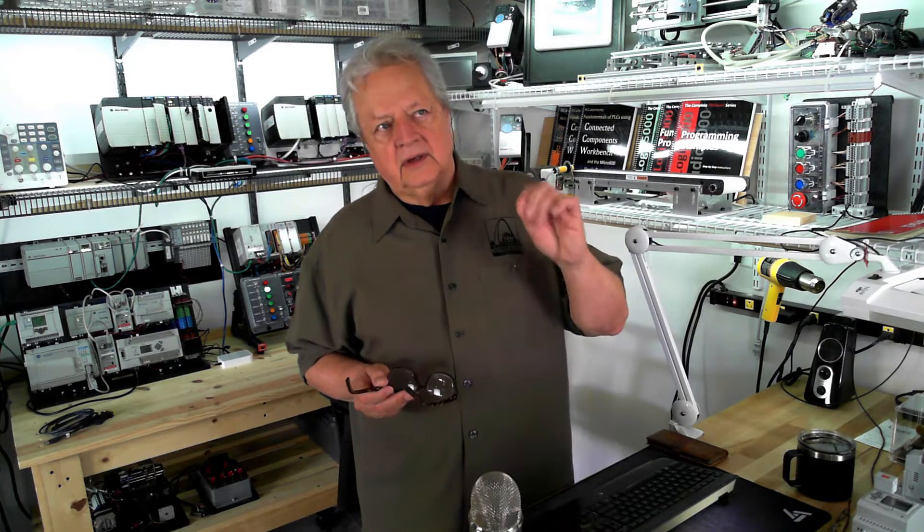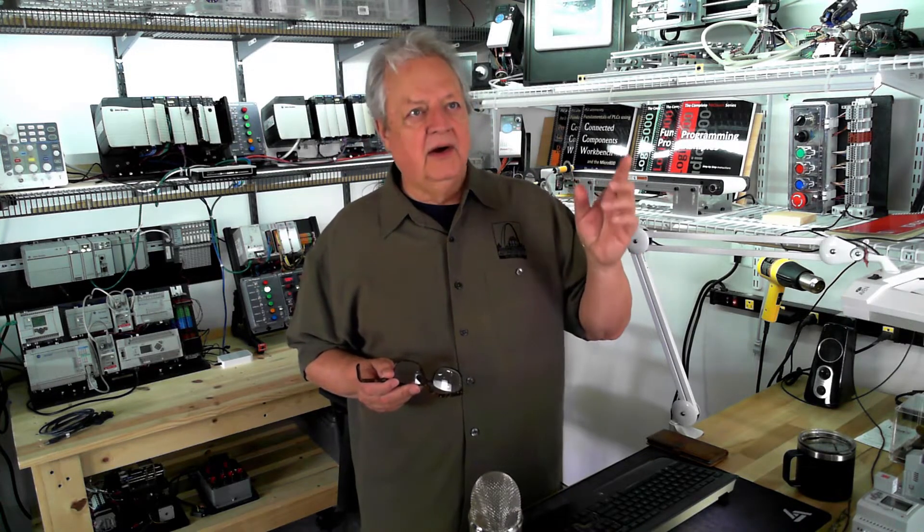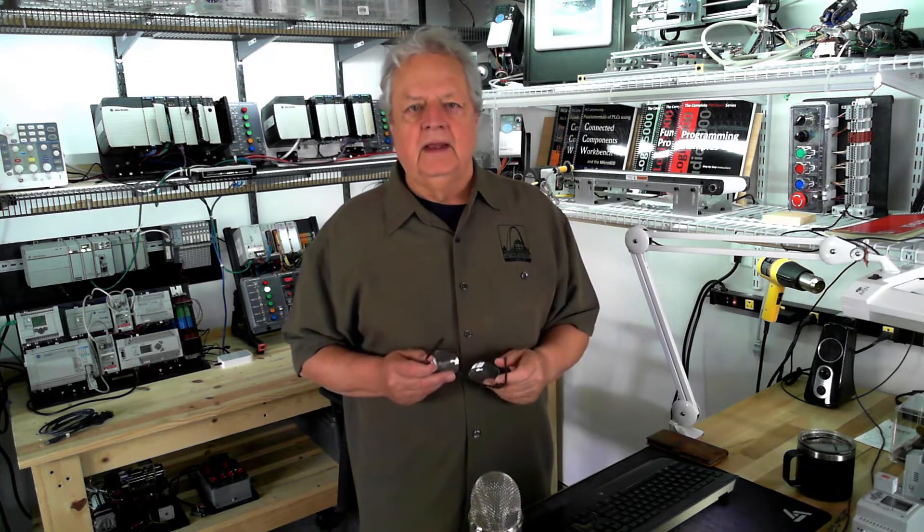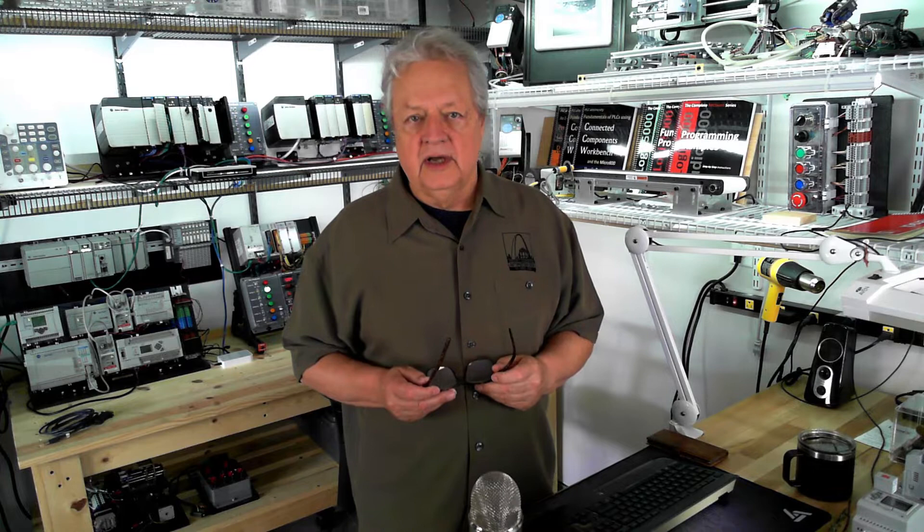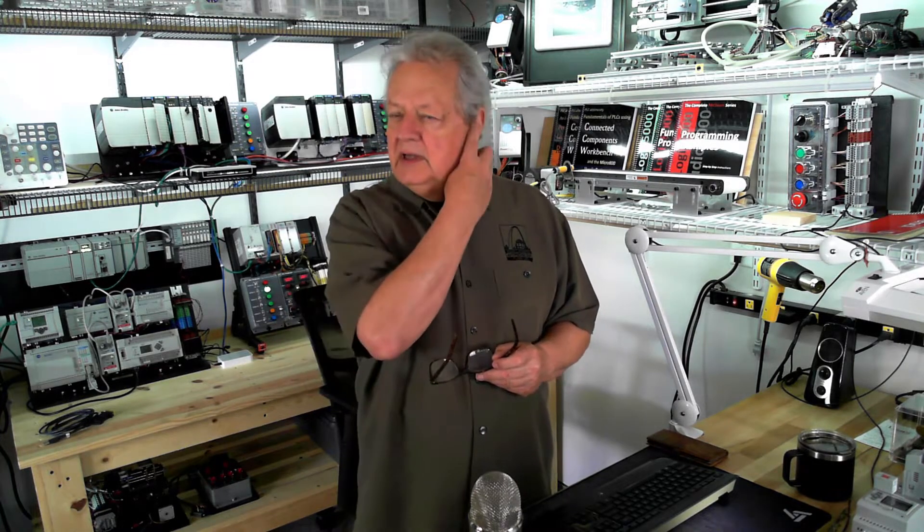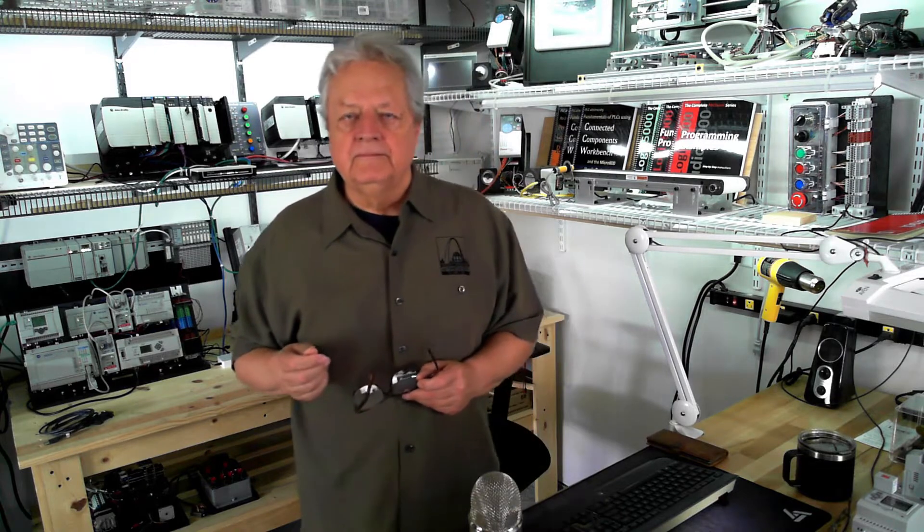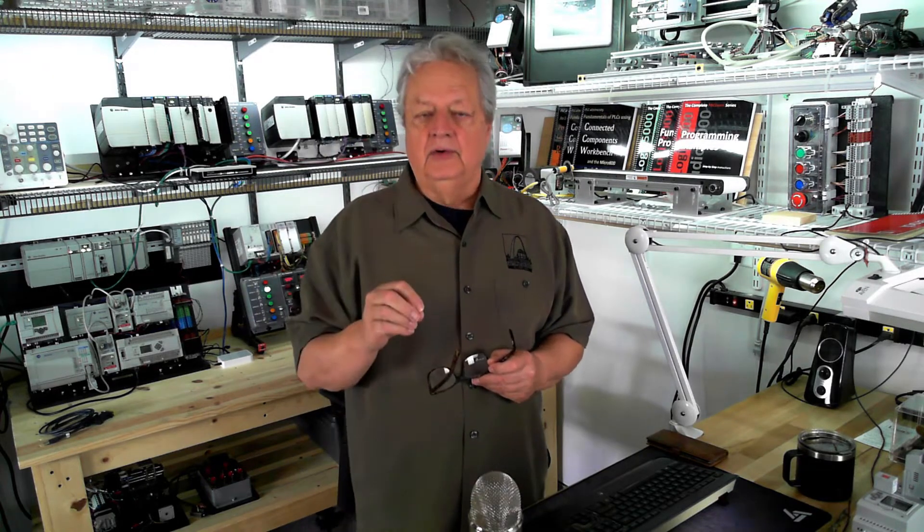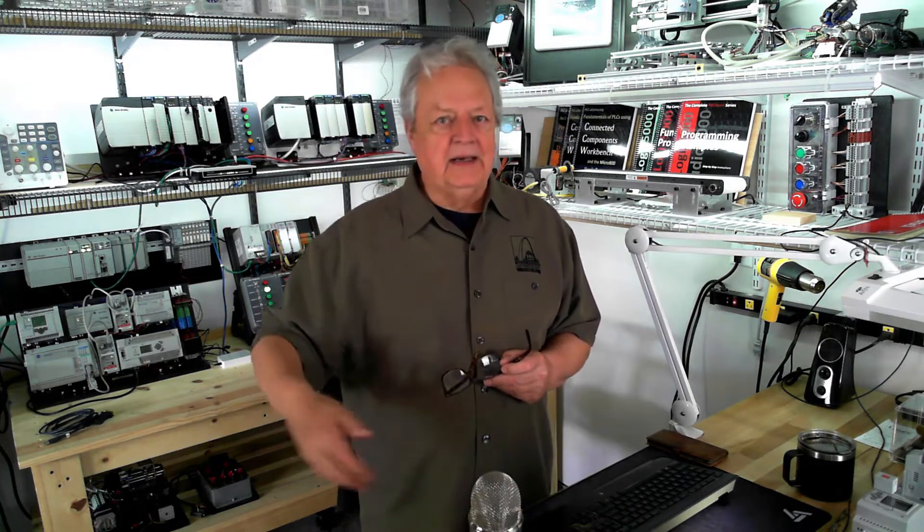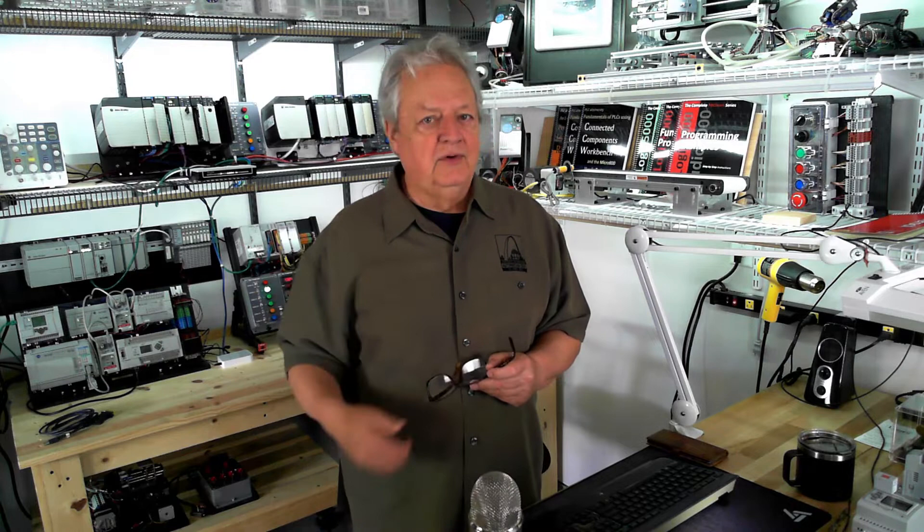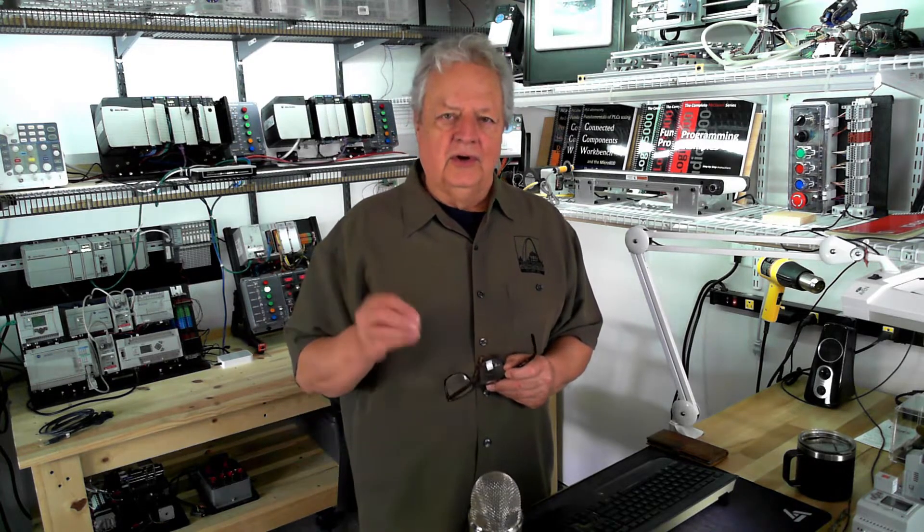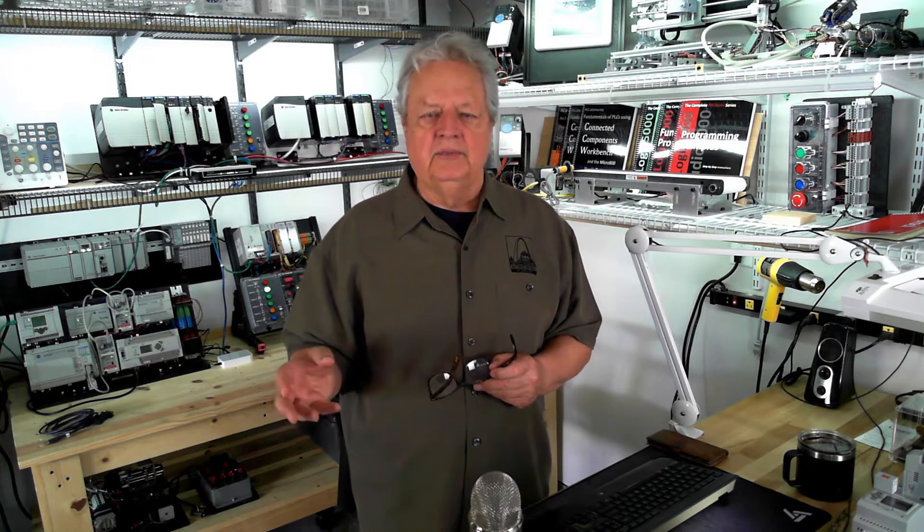You could have more than one rung at a time in the edited mode. The way it works is if you're online editing in run mode, the process is still running—you're still making parts, assembling things, processing food, chemicals, whatever your system is doing. The controller has to keep running and executing the program files, updating IO, everything while you're doing these edits.